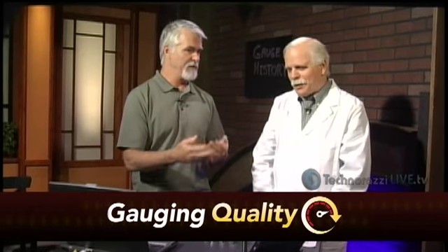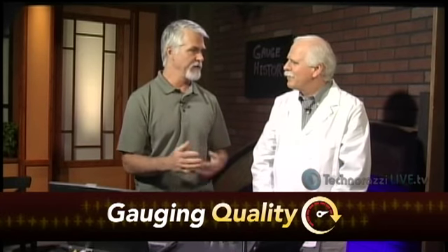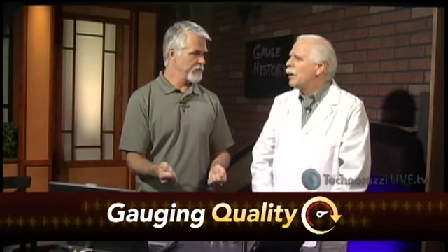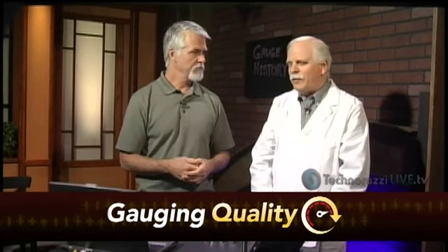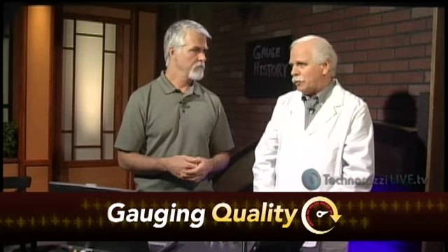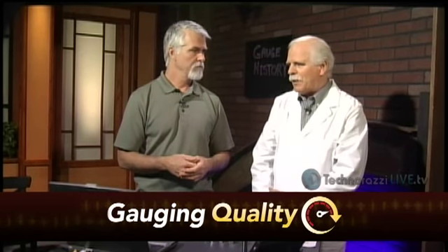Let me touch on this a little bit. The old-fashioned way, and I think we'll talk about this in a little bit, was simply paper and pen, or maybe an Excel spreadsheet, and kind of manually taking your data historically from what, your certs? Typically, we would take them from the data we've collected over the years on the tool and analyze it. If it's just one feature, that's a lot simpler than if it's multiple features. A tool that measures multiple different areas might drift different ways, depending.